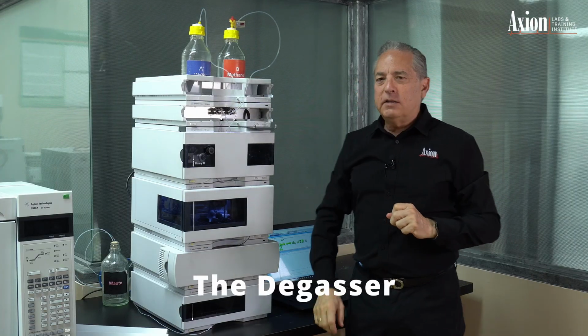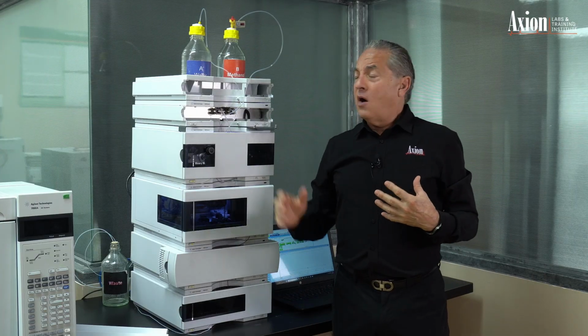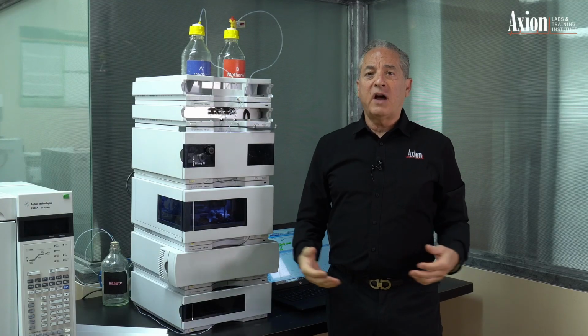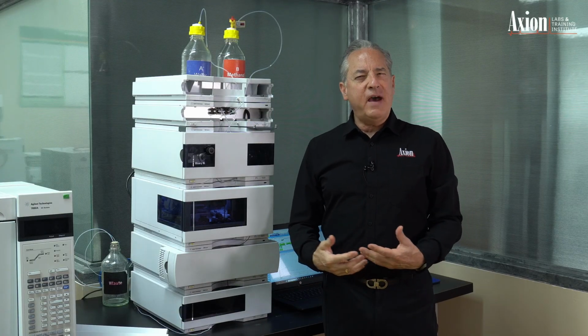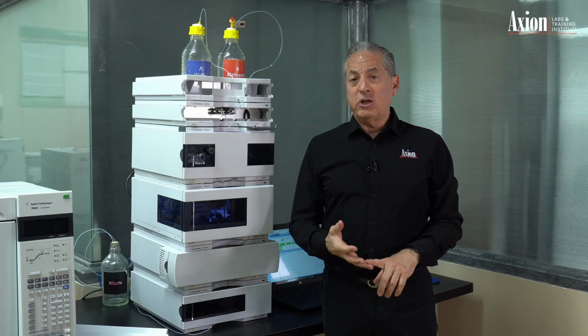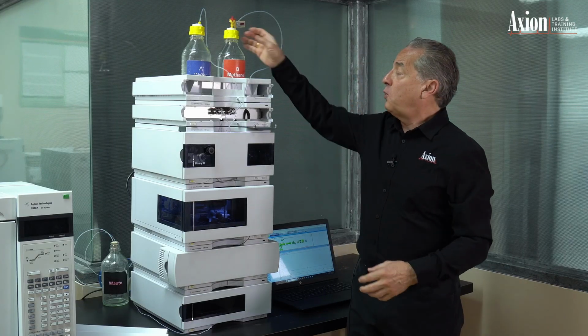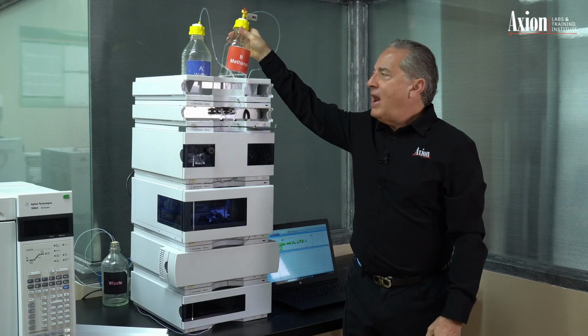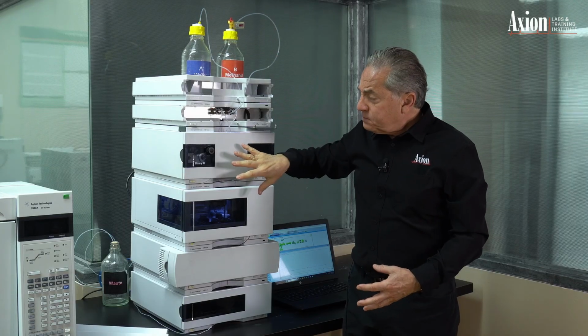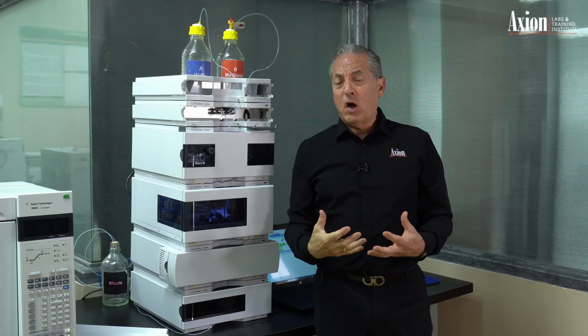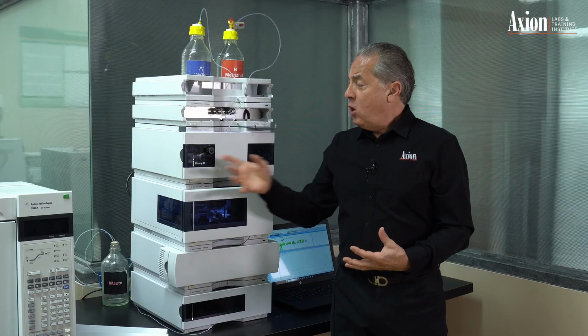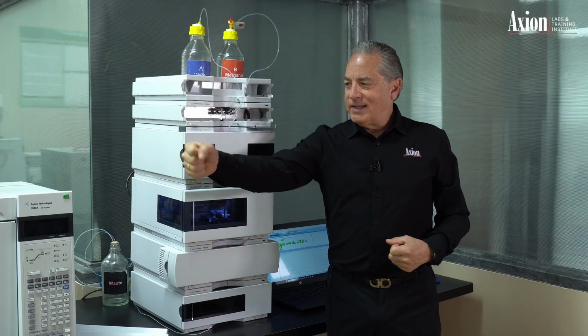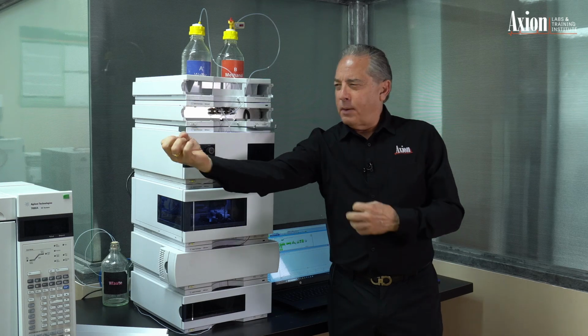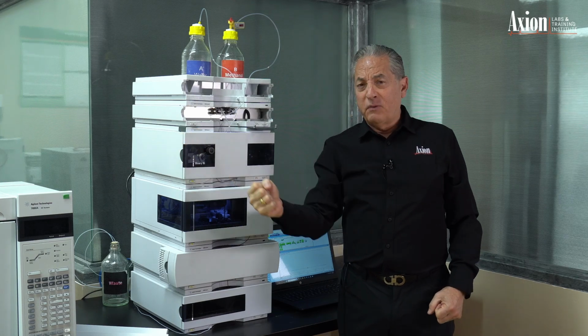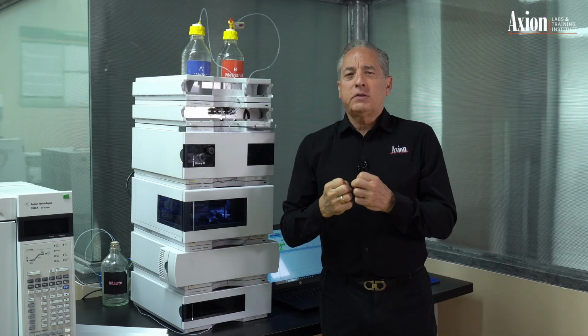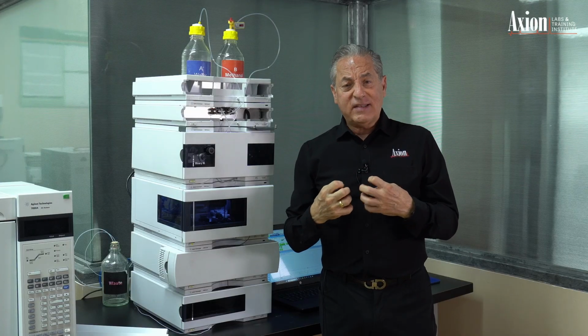The reason why degassing is very important is because our solvents, water, methanol, acetonitrile, at room temperature, room pressure, have dissolved gases. Oxygen, nitrogen, carbon dioxide that are in solution right now in my methanol bottle. Now that's fine until we go to lower the pressure of the mobile phase. And what happens is when the pump goes to draw in mobile phase, it's a syringe and it pulls back, it applies a little bit of a suction and it pulls in mobile phase. When that happens, it will cause dissolved gases to come out of solution as tiny little bubbles.